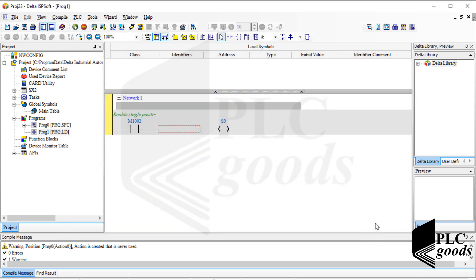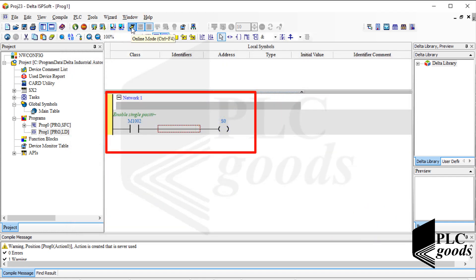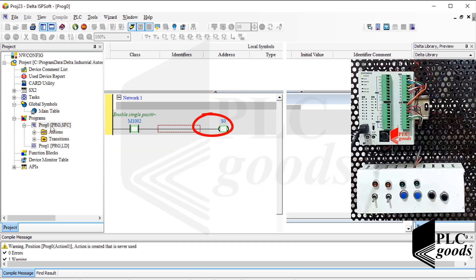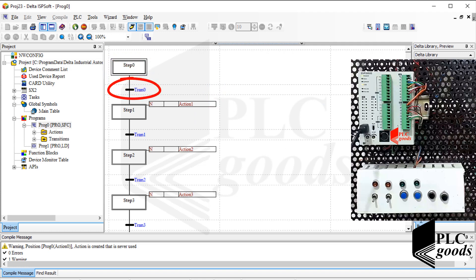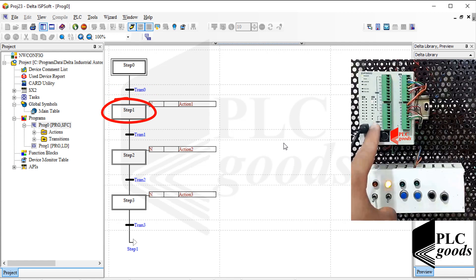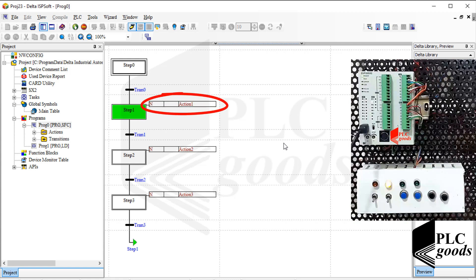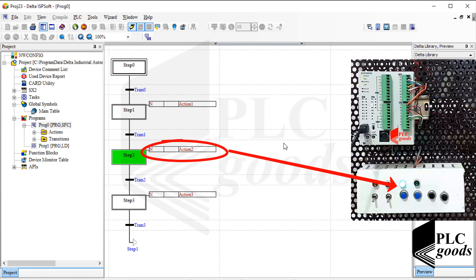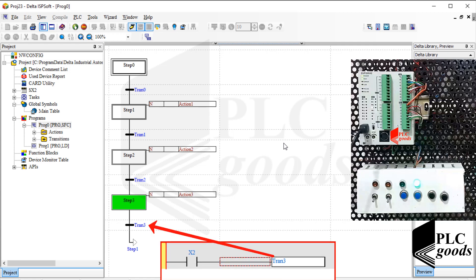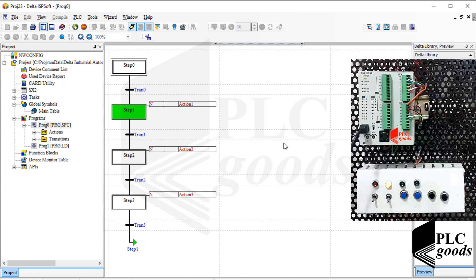The program has been transferred successfully. When I run the PLC, the first step will be executed during the first scan time. The first step doesn't have any action and its transition condition is activated, so the PLC will go to the second step immediately. At the second step, the second LED remains on for 10 seconds, then the transition condition is enabled and the PLC goes to the third step. Similarly, the PLC exits the third step and enables the fourth step. The last transition can be enabled by a digital input — when I press it, the PLC goes back to step 1 and the sequence repeats.